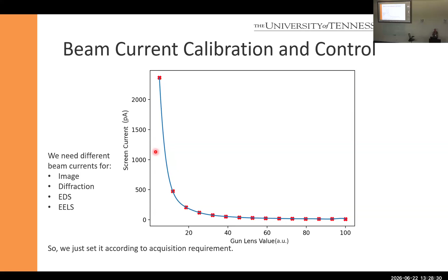So one thing you can do is calibrate your beam current and let it run in a Jupyter notebook, and then you just dial these numbers in, and suddenly you can do things very, very quickly. You do EELS with 50 picoamp, you do EDS with 350, and then you go to 5 picoamp to do your diffraction pattern, and you move backwards and forward. And it does take nanoseconds, of course, right? Because it's a computer. So you want to have that. And it suddenly changes things because now you can do all these different experiments instead of first this, then that. You can do that on the same spot.